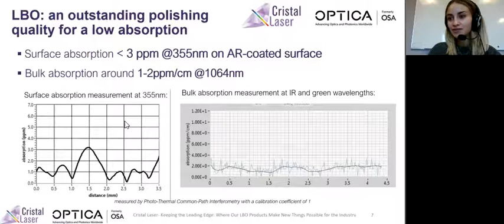So this is a very useful device, and I'm going to present to you a little of how it works. So here's the principle of functioning. There are 2 lasers, one pump laser and one probe laser. The pump beam is going to be absorbed by the crystal, which will produce a local heating inside the crystal and cause a refractive index change, because the refractive index is temperature dependent. The probe laser then undergoes a phase distortion, which is measured, and the absorption of the optical material is derived from the recorded phase distortion.